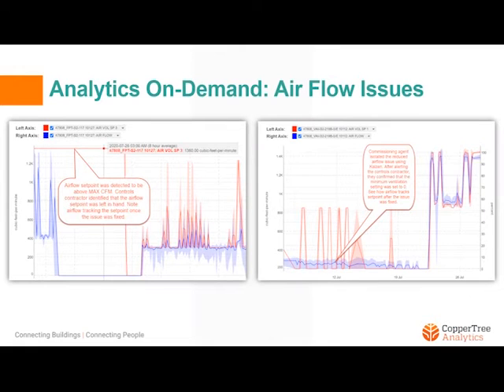For the trend view on the right, we found that a minimum ventilation set point had been incorrectly set, which was resulting in a low CFM. You can see again when this was corrected and the airflow began to track to set point.